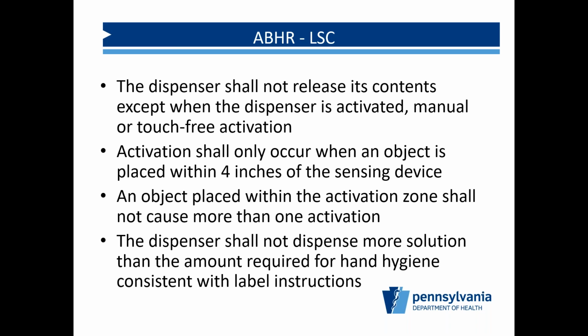A little bit difficult one to control, but a dispenser should not dispense more solution than the amount required for hand hygiene consistent with label instructions. So the idea is to really just make sure it's working properly, and it's not dispensing a ton of hand sanitizer that might be getting down the corridor wall or the room wall and onto the floor and causing issues.